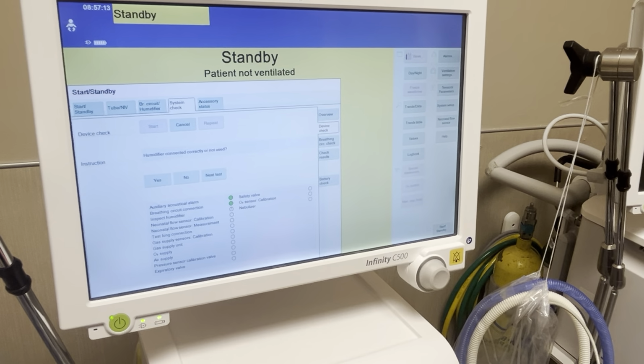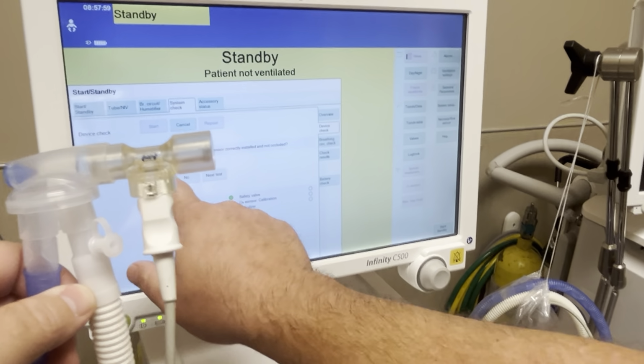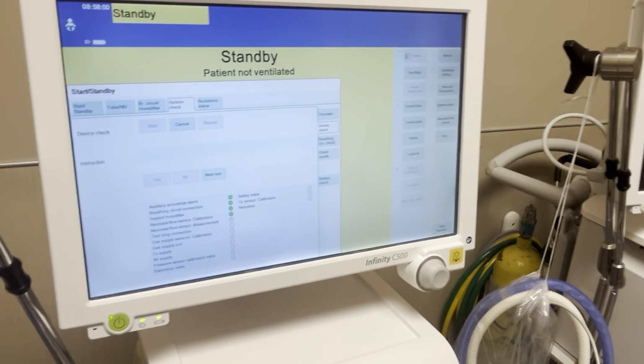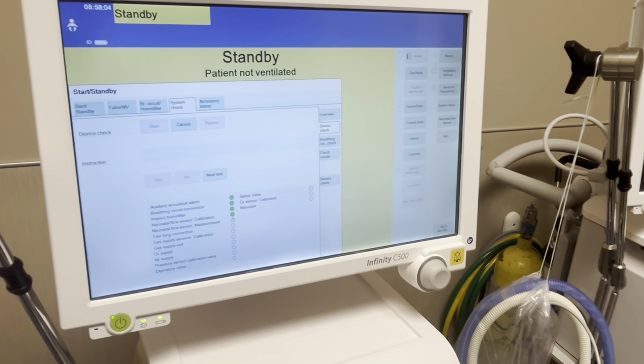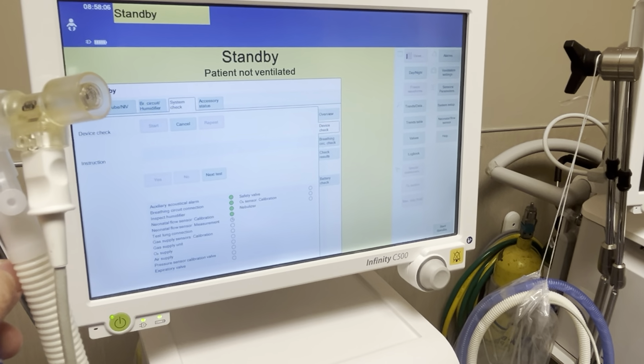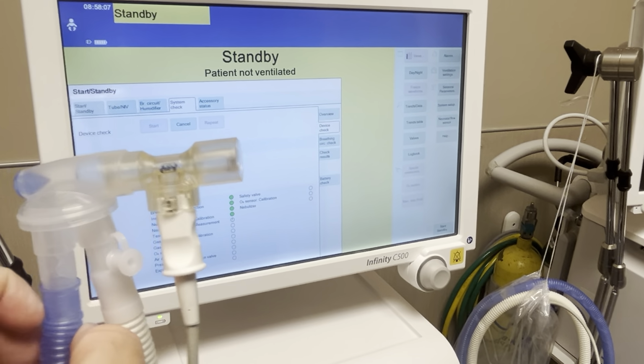So this is gonna zero the flow sensor, which I usually just occlude both ends to make sure it zeroes nicely. Okay. Put it back on. Now it says test lung removed and flow sensor correctly installed and not occluded. So I just put the flow sensor back on. Push yes, and it'll start blowing, making all kinds of fun noise. So now it's just measuring the flow sensor.